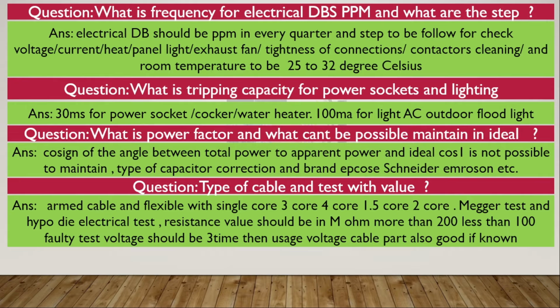If we are getting more than 200, that means our cable is okay, or else the circuit is open. If we are getting less than 100, that means there is a fault somewhere in the cable, maybe a leak or a short circuit, or maybe moisture. There are many factors. You can watch my Megger test video for a better understanding of cable testing.